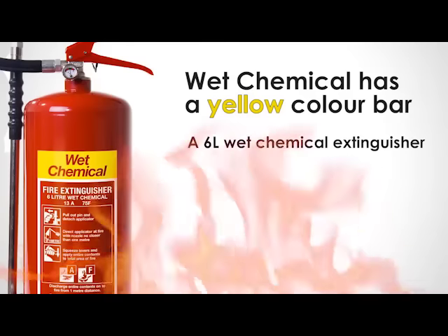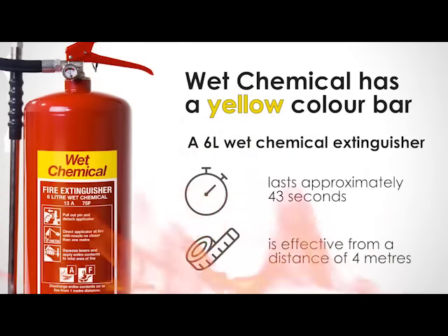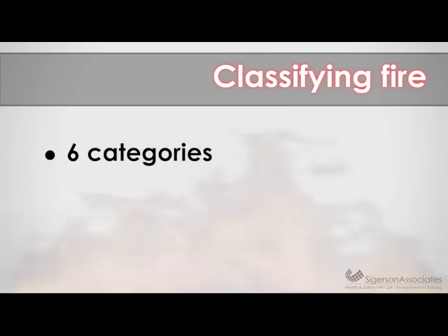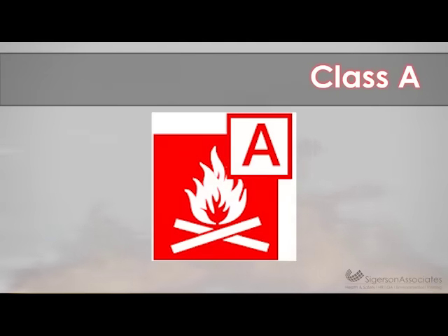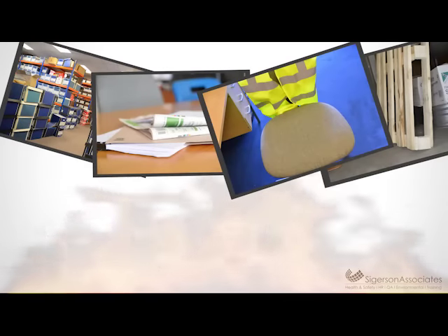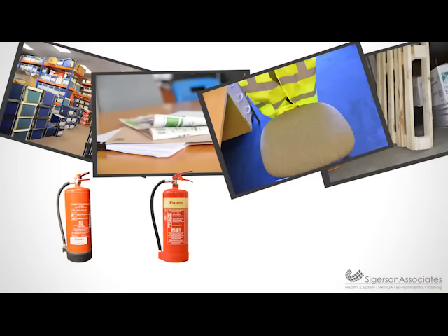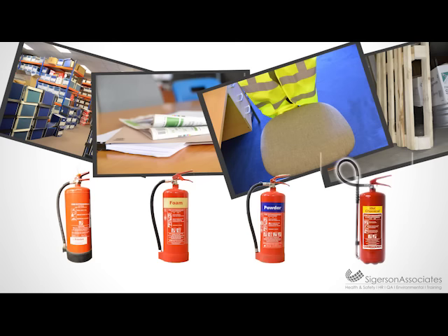A 6-litre total discharge wet chemical extinguisher will last for approximately 43 seconds and is effective from a distance of 4 metres. In terms of classifying fire, there are 6 categories to consider. They are: Class A. Fires involving freely burning materials such as cardboard, wood, paper and textiles. These fires can be tackled by using water, foam, dry powder and wet chemical extinguishers.